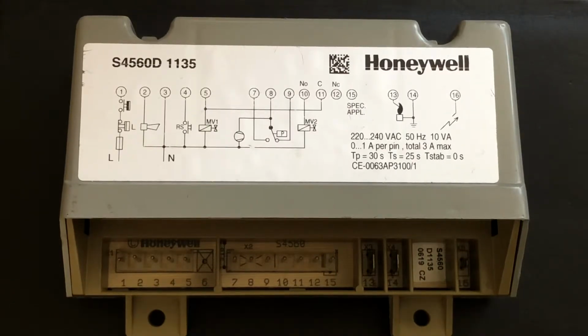Further, you'll have number 7, number 8, and number 9. These are allocated to a differential pressure switch. Number 8 is the common, and the common is a normally closed circuit with number 9. When number 8 supplies power to the fan, number 8 and number 9 should be in short, a closed circuit. When the fan starts, number 8 will be in short with number 7, which is a normally open circuit.